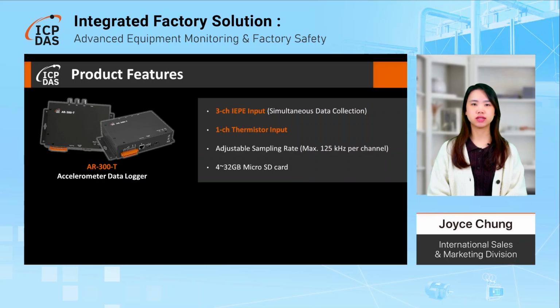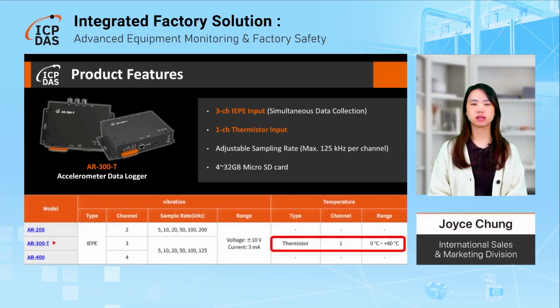The AR300T accelerometer data logger provides 3 IEPE input channels, and it allows simultaneous multi-channel data collection. Compared to the AR400 accelerometer we mentioned in the previous slides, the AR300T module provides one extra function: one channel of thermistor input. The sampling rate of the AR300T module is also adjustable, with the maximum of 125 kHz for each channel. All collected signals are stored on its built-in 4 to 32 GB microSD card for offline vibration analysis.